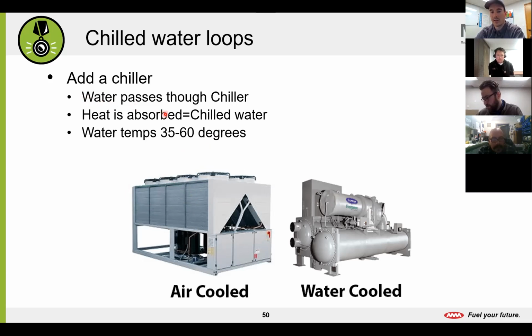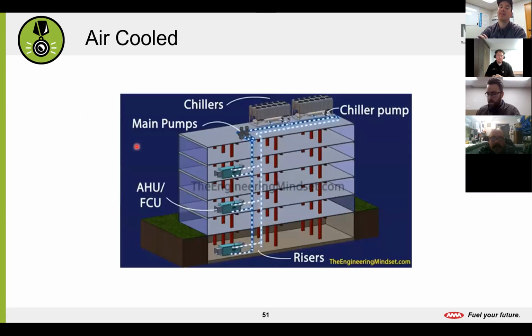So for these chillers, the point of them is to cool down water, to deliver chilled water. A lot of times you'll have them delivered to a fan coil unit or just anywhere where you're going to want cooling in the building. Yep, heat is absorbed. That equals chilled water. Typically, the water temps for your chilled water coils are going to be 35 to 60 degrees. That's pretty normal to see. Move on there. So this is going to show you what a typical air-cooled chiller setup is.